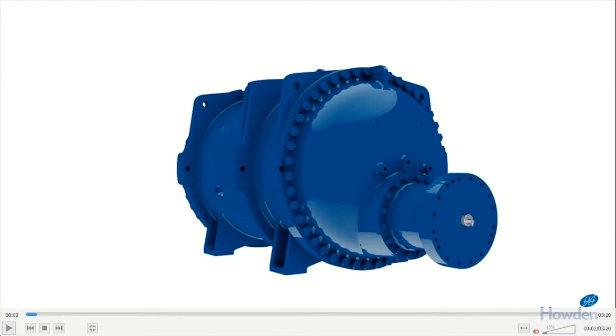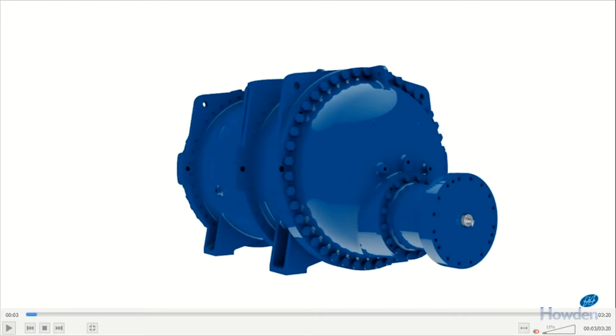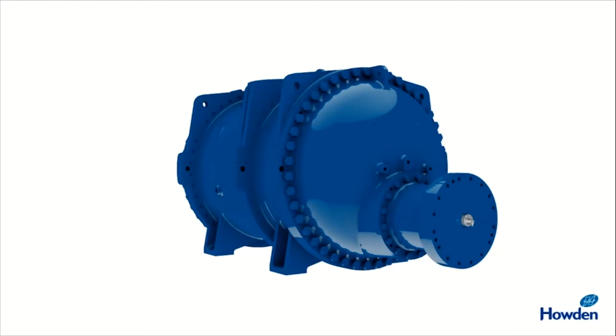You can see in this picture — this is a casing of a Rotary Twin Screw Compressor. This technology of a screw compressor was developed in 1930 by a Swedish company. Inside of this casing, internal components of the screw compressor are installed. The casing is made of cast iron or it can be made of spheroidal graphite iron for special applications.